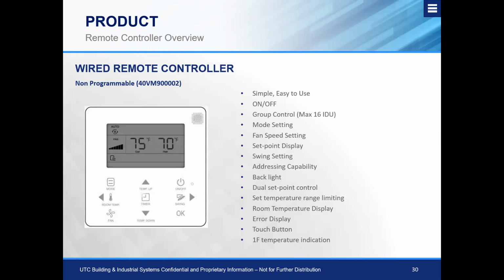Now, with our wired remote controller, pretty much straightforward. The only difference between this and the programmable one is that this one is not programmable. So we have our on and off, we have our mode, set points, and swing features, and of course we also have the ability to get in here and do addressing and see inlet and outlet coil temperatures, the amount of amps that that particular indoor unit is drawing, and return air temperatures. So there's a lot of different functionality on top of being a local unit controller.